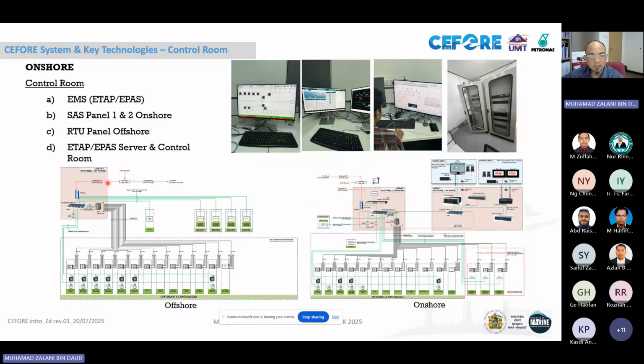We have the fiber optic - actually we use a submarine cable that is a composite cable, so apart from power delivery, it also carries fiber optic. We transfer data from offshore using fiber optic to onshore, landing at the server onshore. There we also collect data and control instrumentation like breakers through the RTU panel. There's an FO ring to communicate from this EPAS server with the onshore servers - this is the EPAS server with the ETAP hybrid PPC.